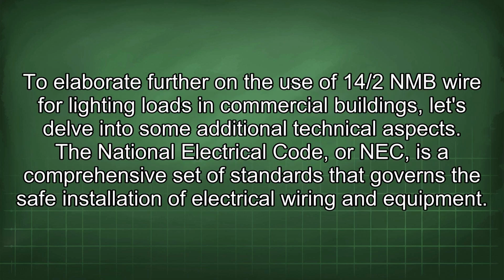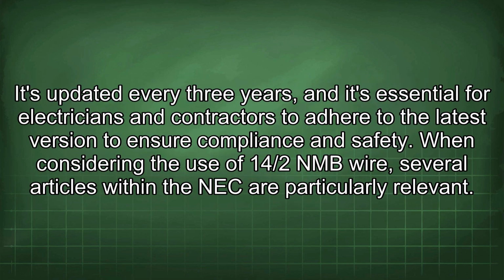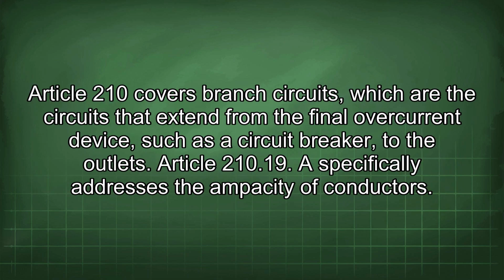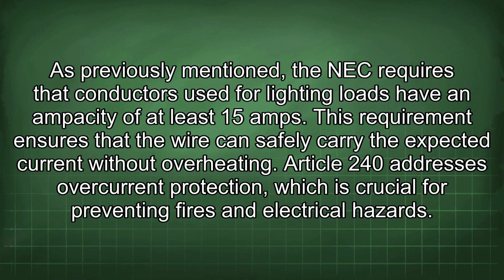To elaborate further on the use of 14/2 NMB wire for lighting loads in commercial buildings, let's delve into some additional technical aspects. The National Electrical Code, or NEC, is a comprehensive set of standards that governs the safe installation of electrical wiring and equipment. It's updated every 3 years, and it's essential for electricians and contractors to adhere to the latest version to ensure compliance and safety. When considering the use of 14/2 NMB wire, several articles within the NEC are particularly relevant. Article 210 covers branch circuits, which are the circuits that extend from the final overcurrent device, such as a circuit breaker, to the outlets. Article 210.19 specifically addresses the ampacity of conductors. As previously mentioned, the NEC requires that conductors used for lighting loads have an ampacity of at least 15 amps. This requirement ensures that the wire can safely carry the expected current without overheating.